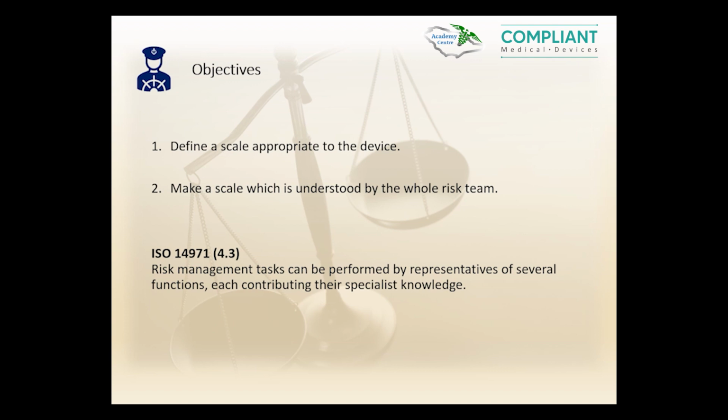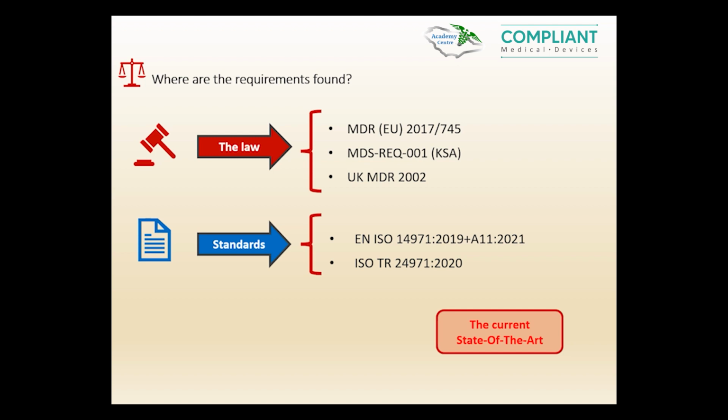The risk team is multidisciplinary, and for most medical devices, the risk team is likely to comprise at least one person from design, production, quality, regulatory, and clinical, and it's quite possible that we will have other functions serving as well, such as installation, servicing, post-market surveillance. For the duration of the risk analysis, we want them all to be speaking the same risk language.